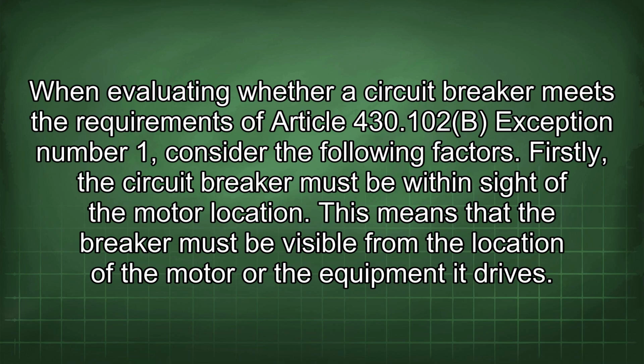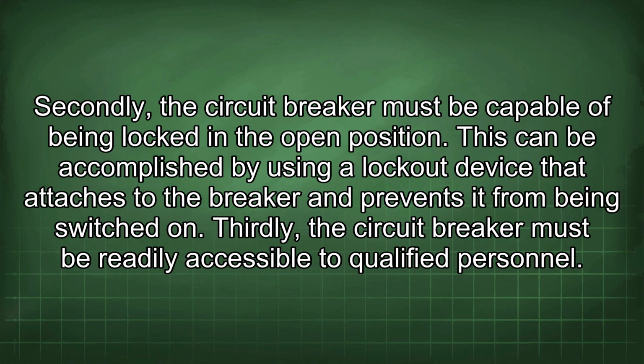When evaluating whether a circuit breaker meets the requirements of Article 430.102(b) exception number 1, consider the following factors. Firstly, the circuit breaker must be within sight of the motor location. This means that the breaker must be visible from the location of the motor or the equipment it drives. Secondly, the circuit breaker must be capable of being locked in the open position.